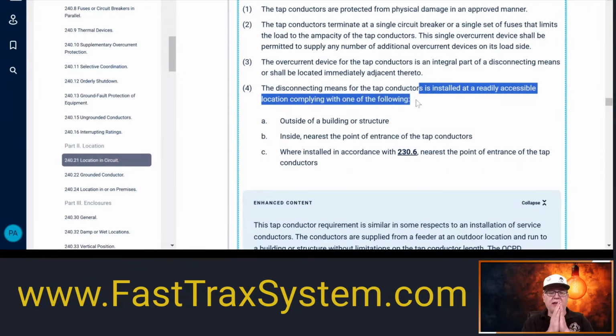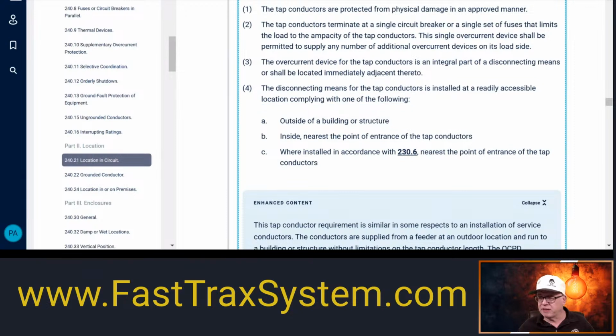So again, whether it's immediately adjacent or all in one cabinet, like a normal panel board enclosure with a main breaker, or a separate disconnect right beside it, not integrated together, either way, the disconnecting means that these tap conductors terminate into has to be in a readily accessible location, not just an accessible location. And you all are familiar with readily accessible as it's defined in Article 100.